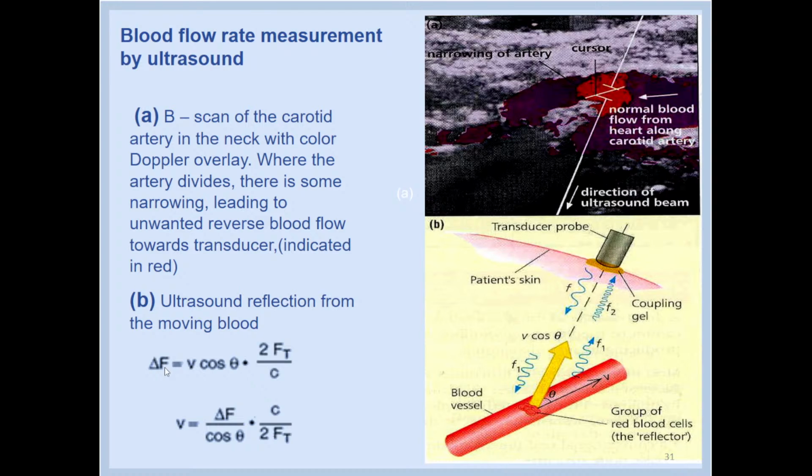is given by the formula shown in the diagram, in correspondence with the component of the blood flow in the direction of the ultrasound beam. This formula. So, blood flow in correspondence with the direction of the ultrasound beam. The velocity of blood is thus computed and its variation with time shown on a spectral Doppler display.